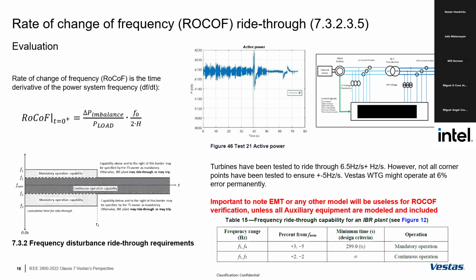So we are here in a dilemma that, okay, ROCOF, similar to phase jump, is not a value that I put in the turbine and say, I ride through 6 or ride through 5. No. The converter, similar to the PLL, will produce some certain frequency. And when that frequency is outside the clause 7.3.2, that is the disturbance ride-through requirement, the normal operation, then you eventually will trip. So if we can withstand 6% in our technology, 6% is 3.6 hertz. So as long as that ROCOF doesn't reach 3.6 hertz, so if it's at a rate of 5 hertz per second, it will reach 5 hertz extra in 1 full second. So it will be around 0.68 seconds that it will reach that.